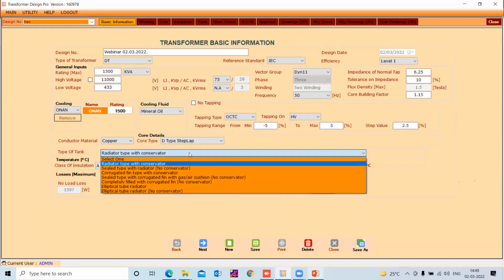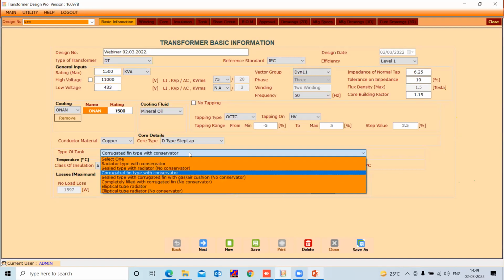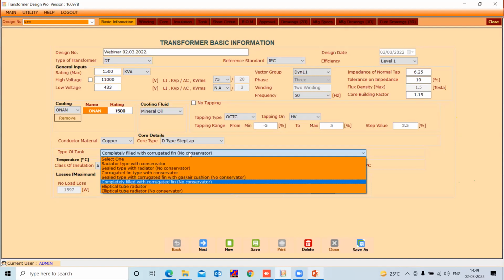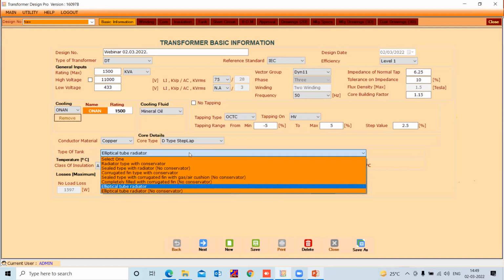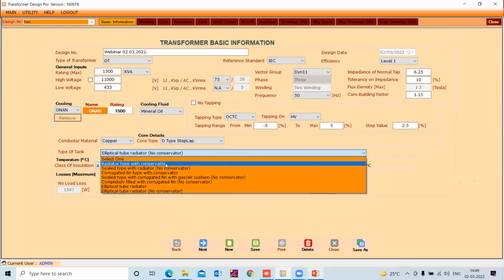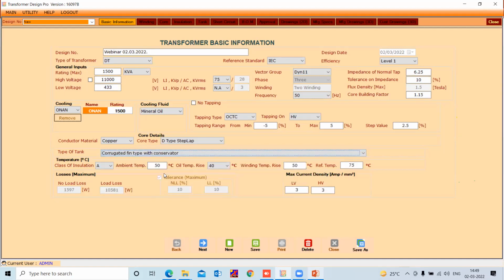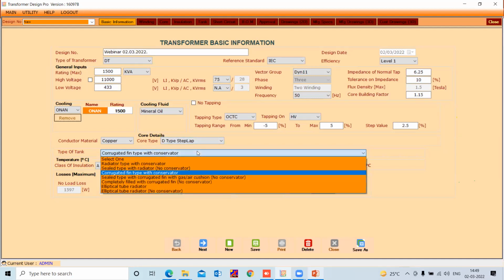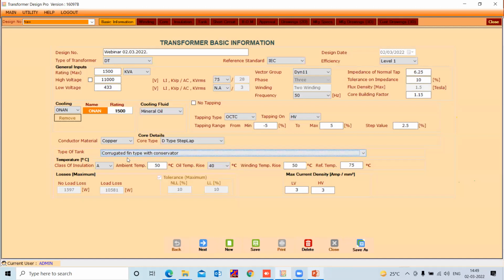Okay, then let us go to the type of tank. For type of tank, you see radiator type with conservator. You can see the sealed type without conservator. You can see the corrugated fin with conservator. Sealed type without conservator, completely filled with corrugated fins without conservator. You can go for the elliptical tube radiators. You can go for elliptical tube radiator where there is no conservator. All these options are there as part of it. When you go for the dry type, obviously you will have the further options whether you want to go with tank or bare without tank. Okay, so let's choose any one that you wish to.